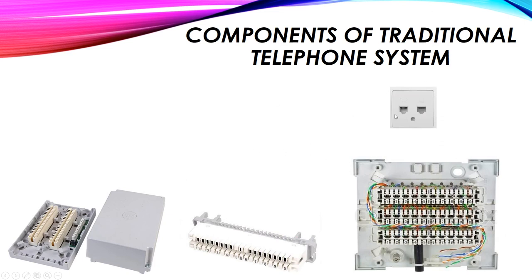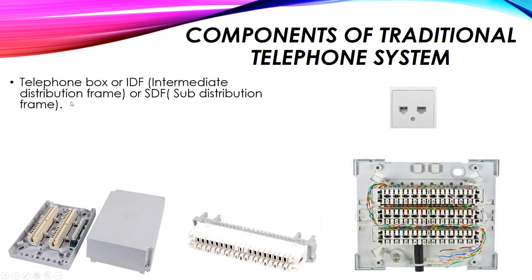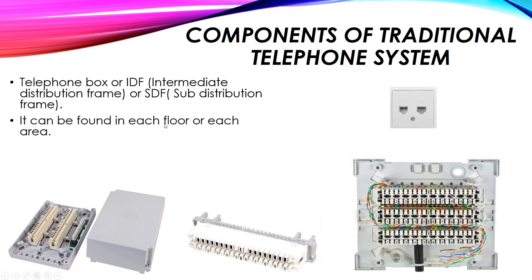The RJ11 outlet is connected to the Sub Distribution Frame, also called the SDF, the telephone box, or the IDF — Intermediate Distribution Frame. The SDF supplies the signal to each RJ11 outlet and is used for collecting and arranging all telephone lines on a floor or in a specific area. It can be found on each floor or in each area, with each RJ11 representing one telephone line — for example, RJ11 number one for telephone one, number two for telephone two in another room, and so on.